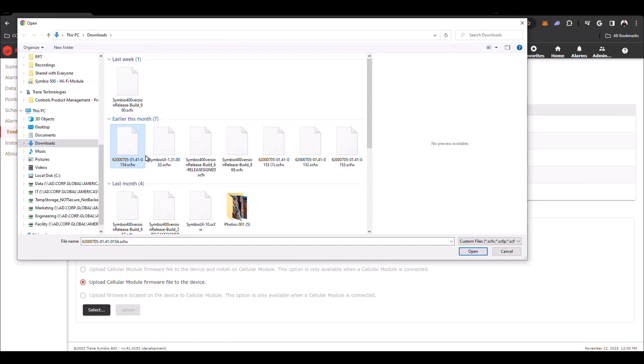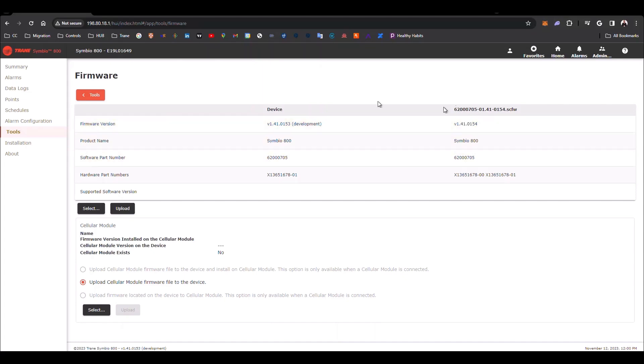Please note this file is a full version — the extension is .scfw. You can select Open. You will see we are moving from the version ending in 3 to the version ending in 4 in this case. Now we click Upload. Here we have a warning message — we can click Continue. We have to wait until the file is uploaded to the controller. We have to start a reboot procedure and the CBA UI will restart. The CBA UI will show you that the version was successfully uploaded.